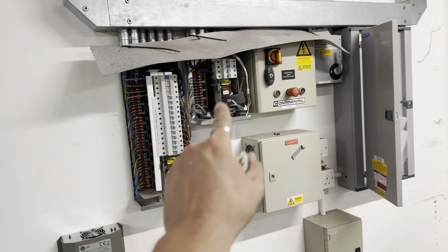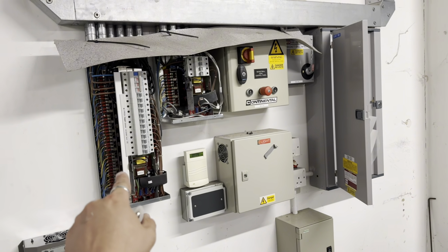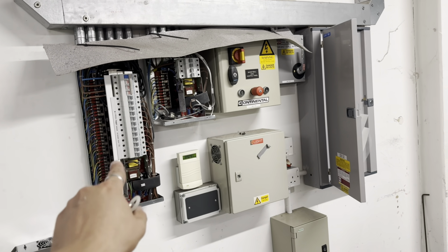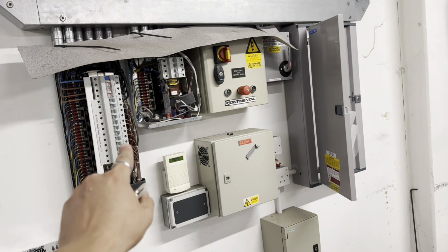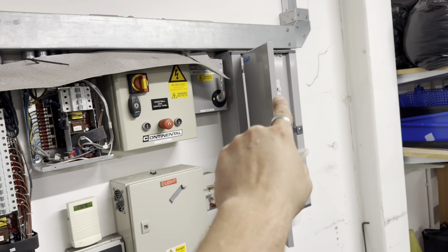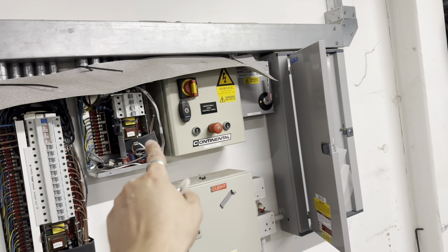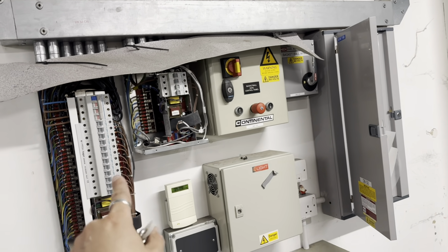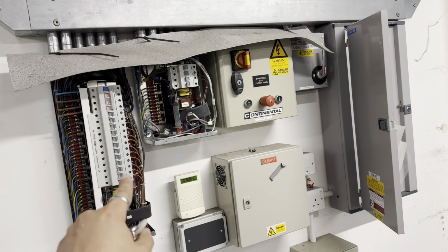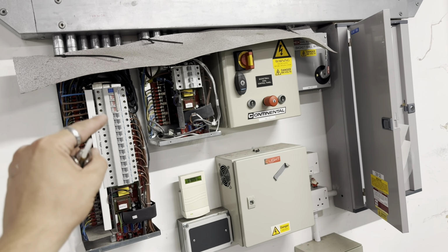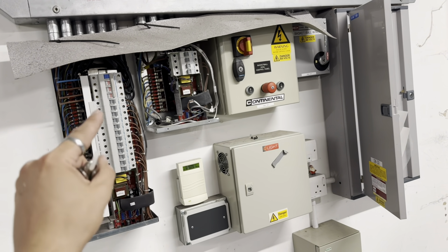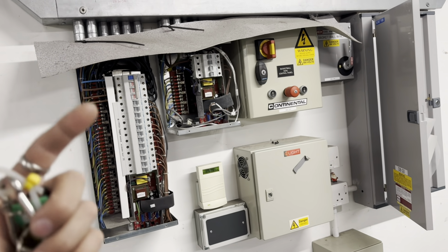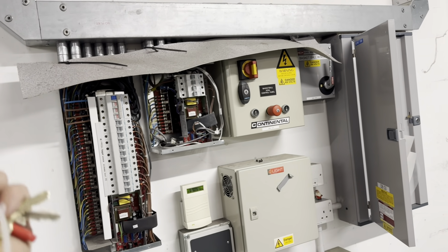In here at the mains - let me flip you around - that rack and that rack are staying. We're getting rid of all these terminals here, just using them for the circuit breakers, so you've got a 3-phase breaker and a single-phase breaker from there. Single-phase feeds that one, 3-phase feeds this one. These are just going to be individual breakers. Each MCB does either 3 or 4 lights, so it's all split down across them, so if there's a fault it doesn't take out the main MCB and they lose all the lights.